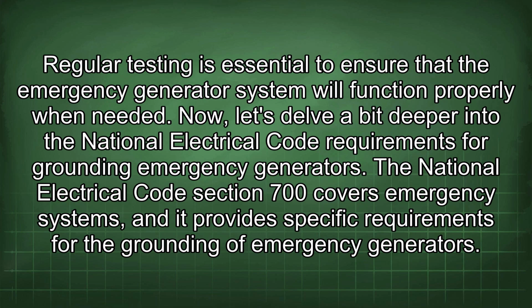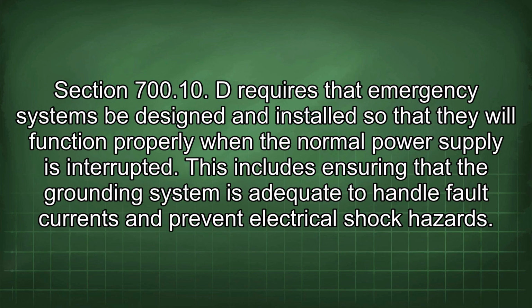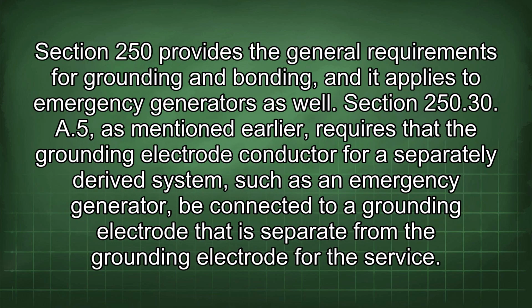Now let's delve a bit deeper into the National Electrical Code requirements for grounding emergency generators. The National Electrical Code Section 700 covers emergency systems, and it provides specific requirements for the grounding of emergency generators. Section 700.10 D requires that emergency systems be designed and installed so that they will function properly when the normal power supply is interrupted. This includes ensuring that the grounding system is adequate to handle fault currents and prevent electrical shock hazards. Section 250 provides the general requirements for grounding and bonding, and it applies to emergency generators as well.